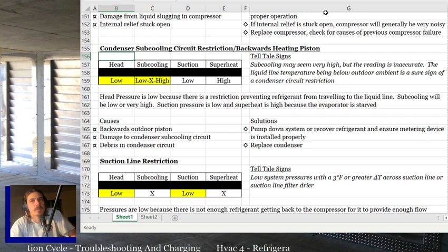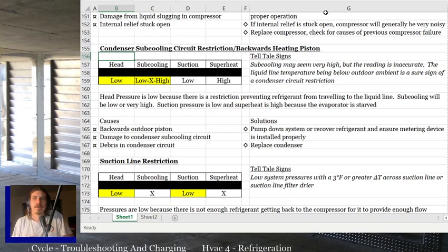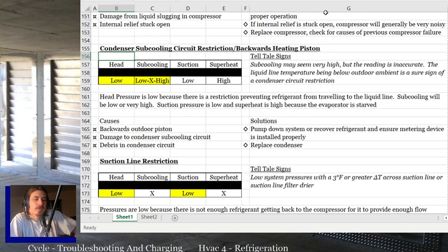Causes: a backwards outdoor piston, damage to the condenser subcooling circuit, or debris in the condenser circuit. Solutions: pump it down, recover refrigerant, and ensure the metering device is installed properly. If you've got an outdoor TXV, make sure that it's operating properly. All that stuff, but make sure that metering device is good and it's working. If the metering device is good and it's working, replace the condenser or that section and piping or whatever you need to do.